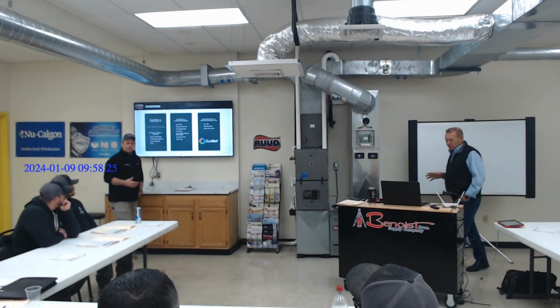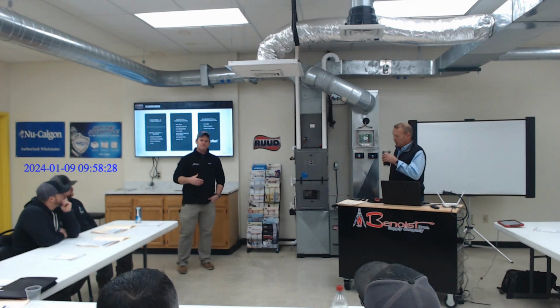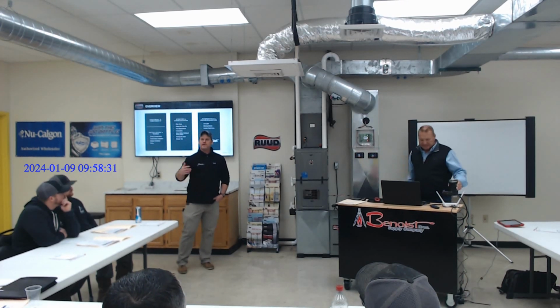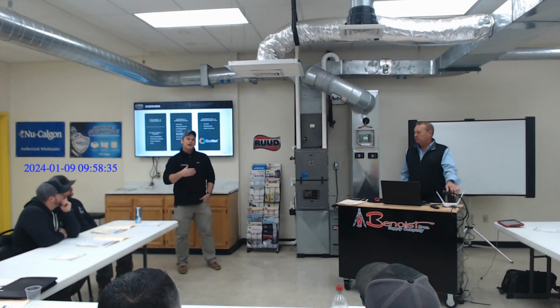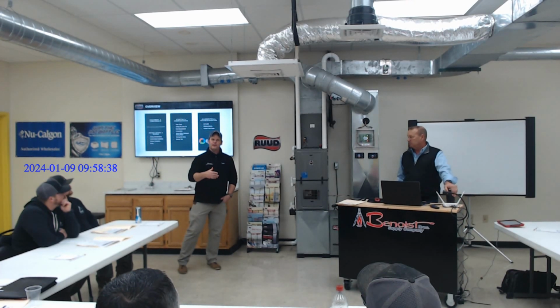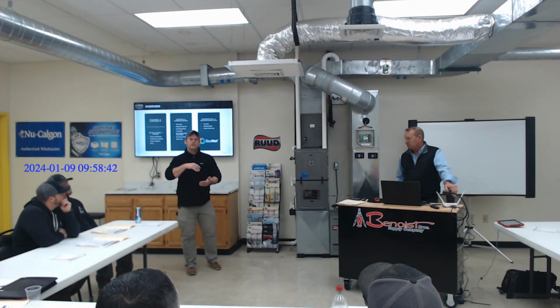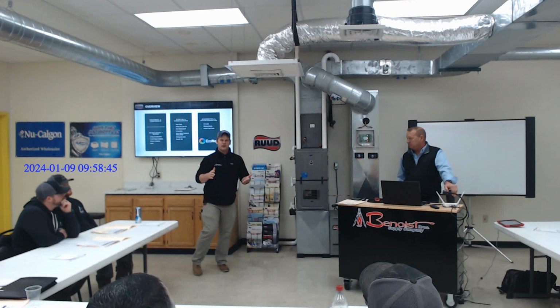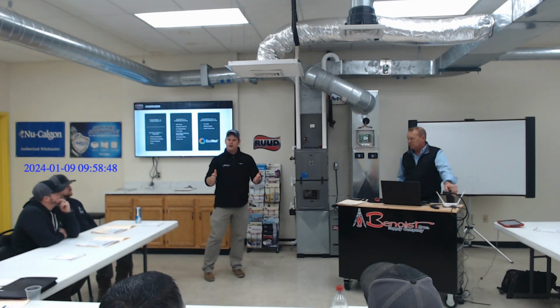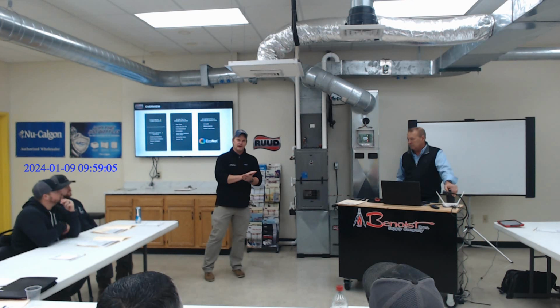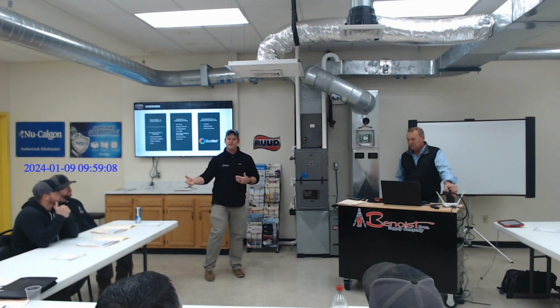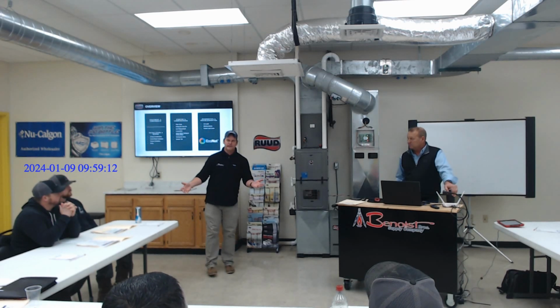A lot of people don't understand that RPM that we're talking about. It doesn't necessarily mean speed. Okay? We can't think like PSC, the faster we're going, the more air we're moving. The constant torque in your variables, as we understand, we are trying to keep a certain CFM. So that RPM change is to keep, let's say we're trying to keep 950 CFMs, all right? That RPM change is going to change depending on how much static it's faced with to keep that CFM. So it's not a PSC motor, the faster speed, the more air we move. A constant torque is trying to achieve a certain CFM by the speed, or the RPM, that it runs, depending on the static that it's facing. You guys got that? Good on that?